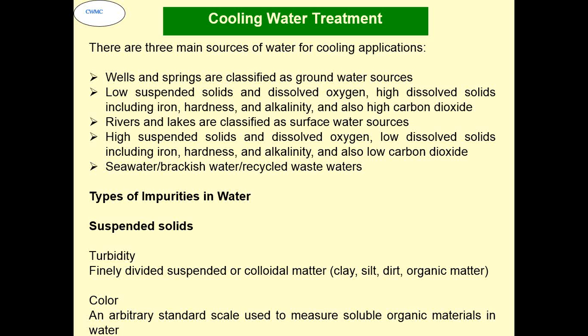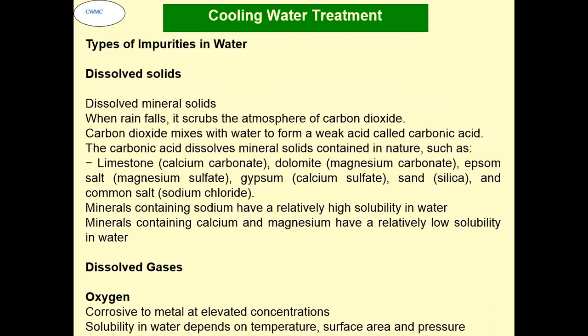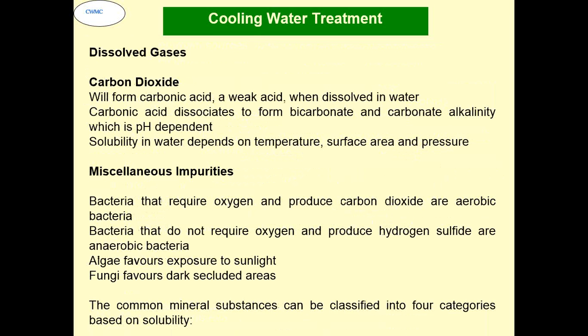Types of impurities in water are generally suspended matter like turbidity and color, dissolved solids, and dissolved gases like oxygen and carbon dioxide. Miscellaneous impurities include bacteria. Bacteria which survive in the presence of oxygen are aerobic bacteria, and bacteria which survive in the absence of oxygen, producing hydrogen sulfide, are anaerobic bacteria. Algae favors exposure to sunlight. In your cooling tower, you would have observed more algae on the portion facing the sunlight compared to the darker side. Fungi favors dark secluded areas.